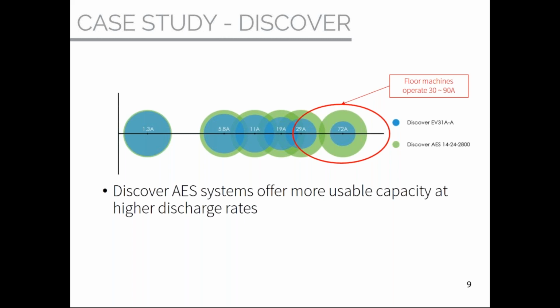Most lead acid packs have their data sheets published at 100% depth of discharge, with capacity ratings as high as the 120-hour rate down to the 1-hour rate. A lot of battery users refer to their lead acid batteries at the 20-hour rate, more to the left of the spectrum here. So you might need to discharge at 1.3 amps or 5.8 amps to actually achieve that 20-hour rate.